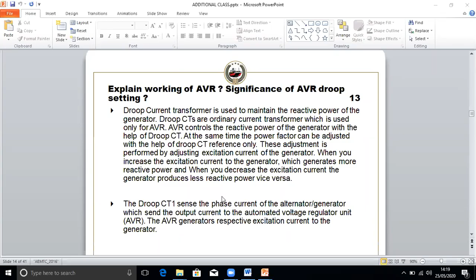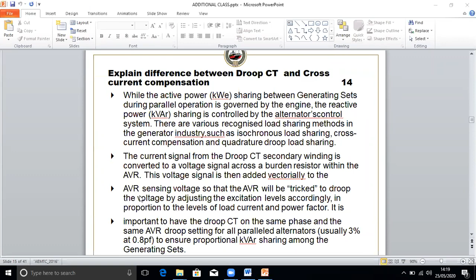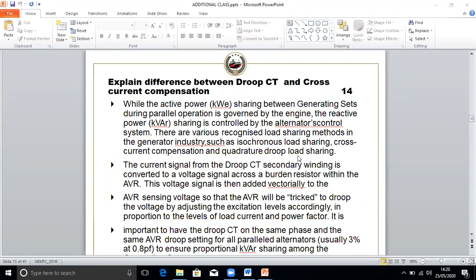Cross current compensation and droop CTs are two different ways of sharing reactive power. Droop CT is sharing reactive power, cross current compensation is also sharing reactive power. Active power sharing between the generator sets during parallel operation is governed by the engine, while the reactive power sharing is controlled by the alternator's control system. There are various recognized load sharing methods in the generator industry, such as isochronous load sharing, cross current compensation, and quadrature droop load sharing. These are the two methods of load sharing, droop CT and cross current compensation.